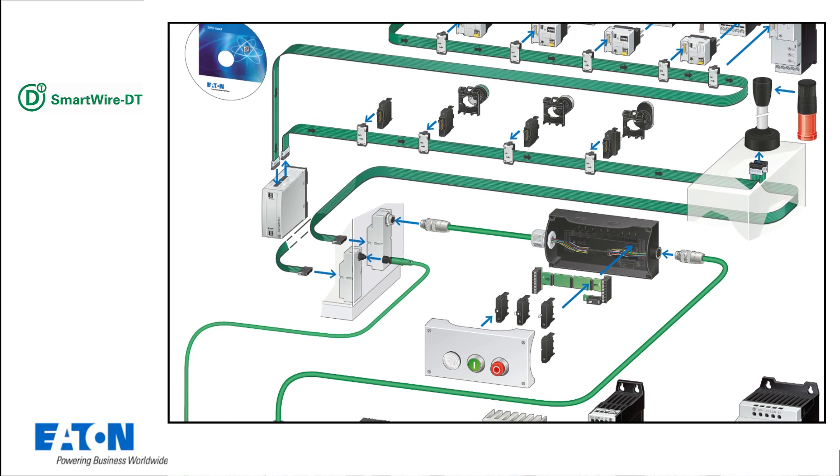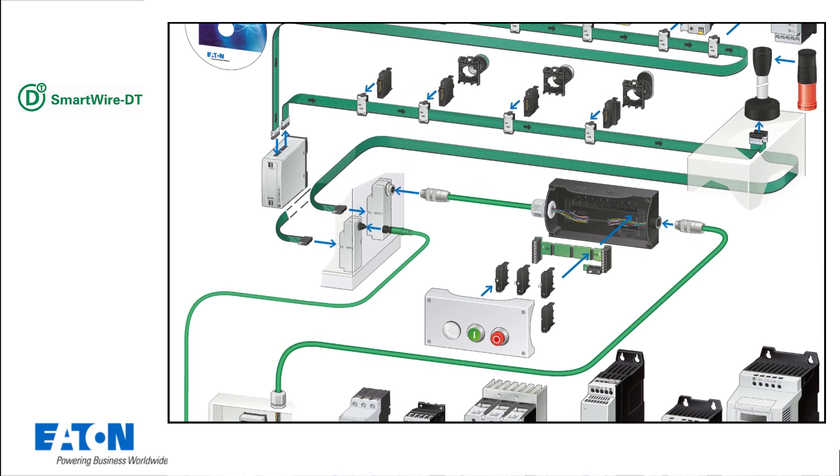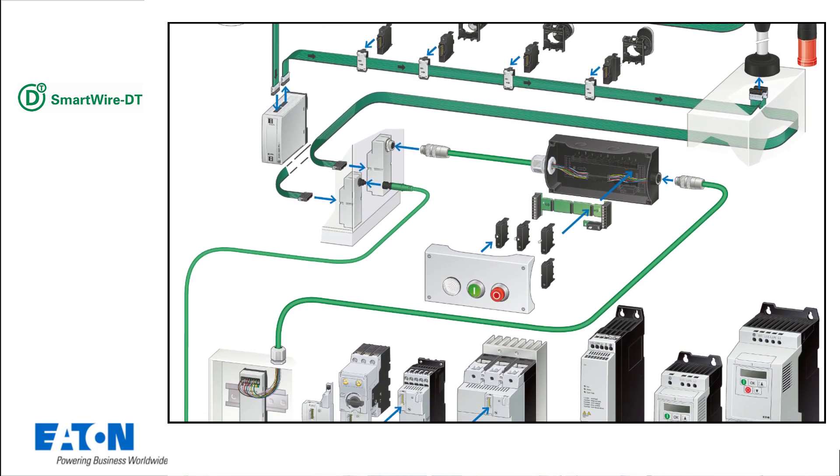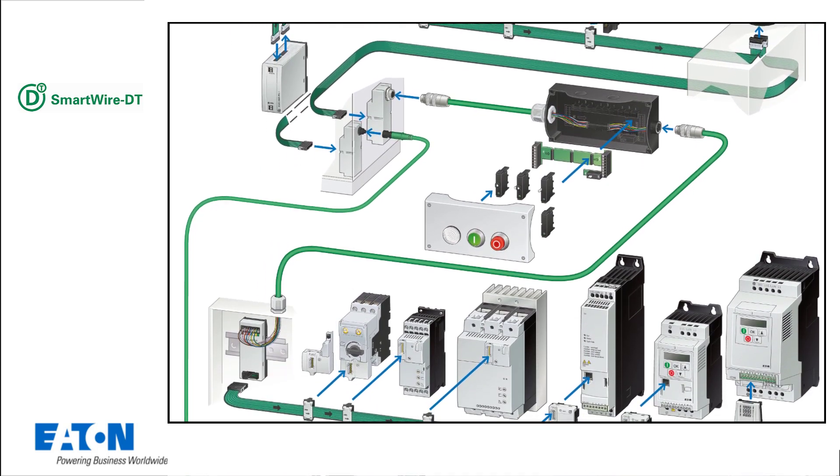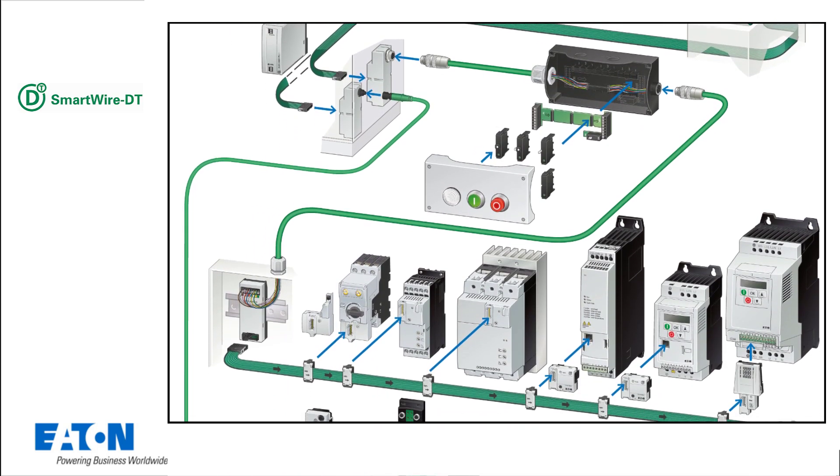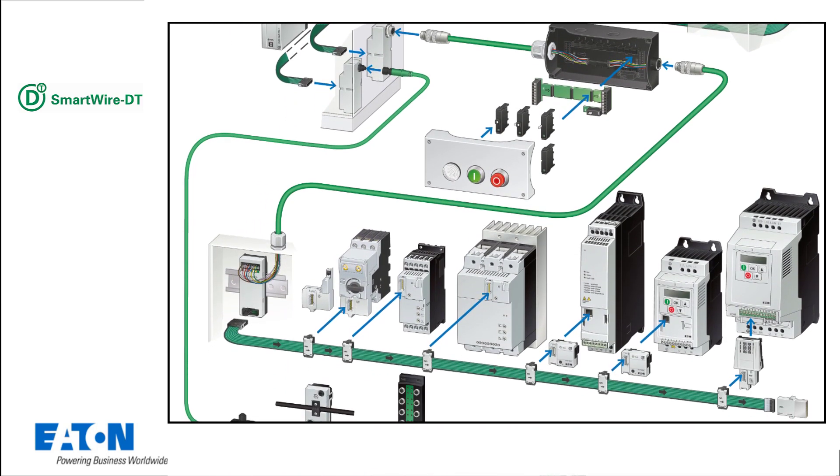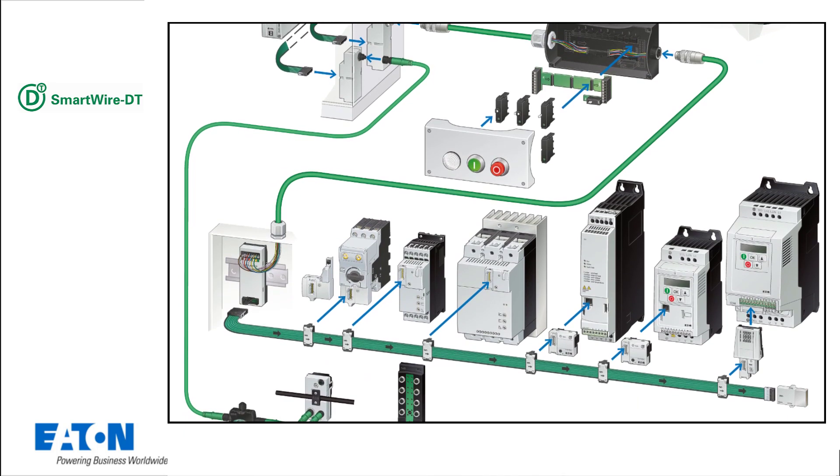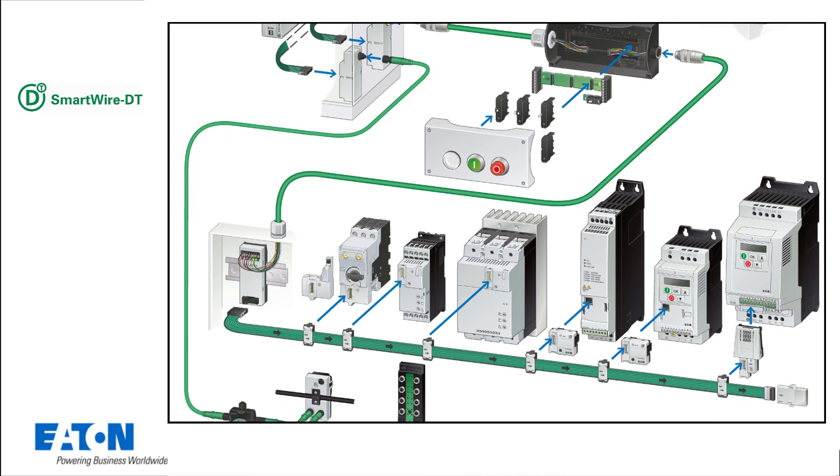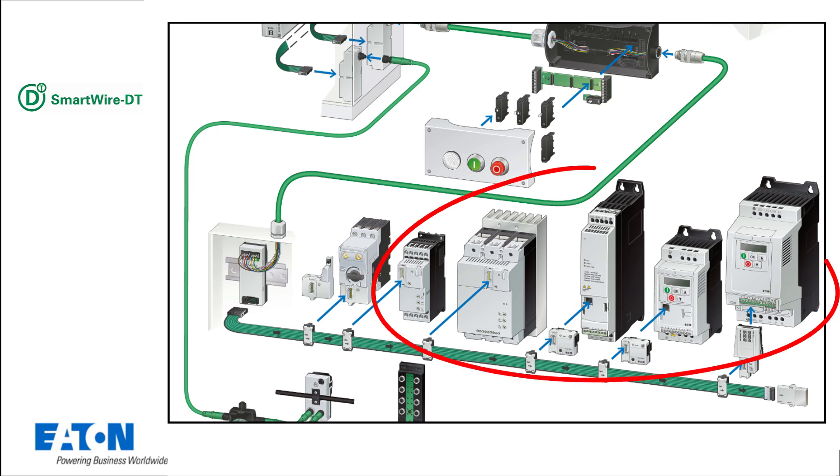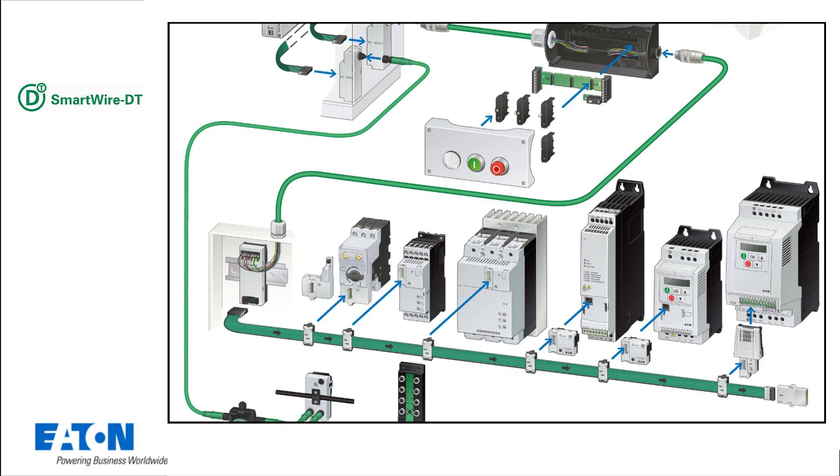The SmartWire DT modules are connected to each other via a green flat cable inside the control cabinet or outside it via a green round cable. An SWD line can extend up to 600 meters. Up to 1000 bytes of user data are available in one telegram. Parameters for DS7 soft starters and DE1, DC1 and DA1 frequency inverters can be easily adjusted.